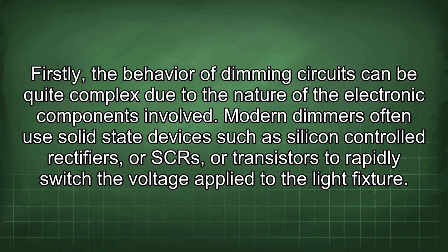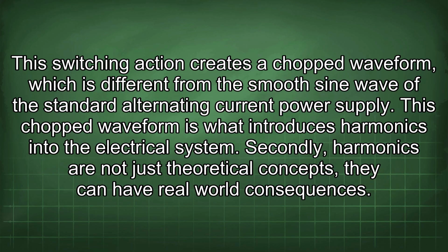Modern dimmers often use solid-state devices such as silicon-controlled rectifiers, or SCRs, or transistors to rapidly switch the voltage applied to the light fixture. This switching action creates a chopped waveform, which is different from the smooth sine wave of the standard alternating current power supply. This chopped waveform is what introduces harmonics into the electrical system.